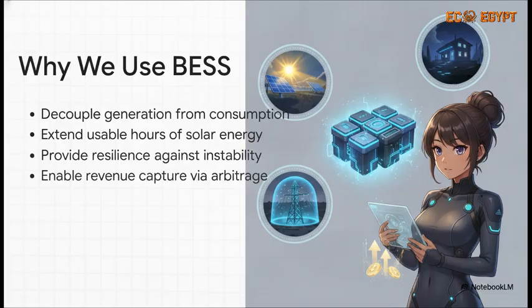First, it decouples generation from consumption. You can capture that huge midday solar peak and actually use it at midnight. Second, that obviously extends the usable hours of your solar. Third, it gives us some serious resilience against grid instability. It's like a heavy anchor when the utility grid starts to wobble. And finally, the moneymaker. It enables revenue capture through energy market arbitrage. You buy or store power when it's cheap and discharge it when prices spike.